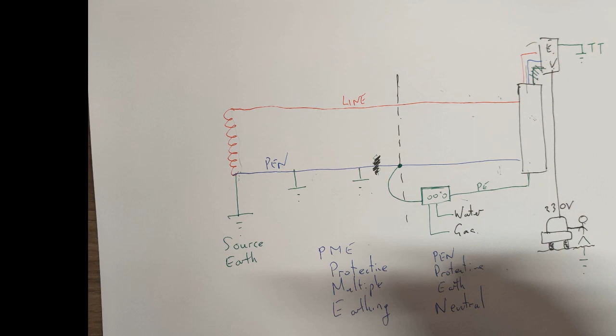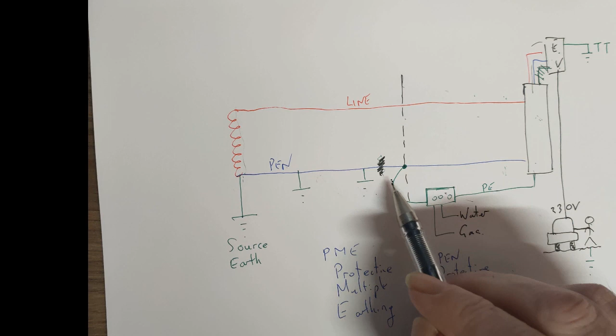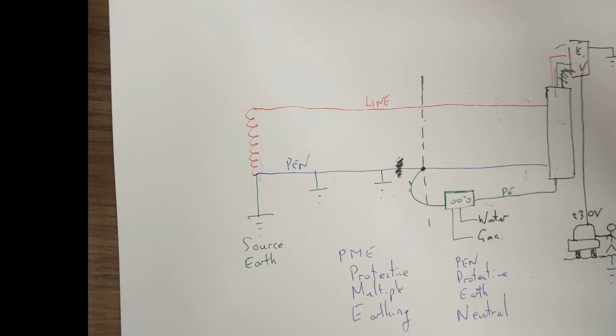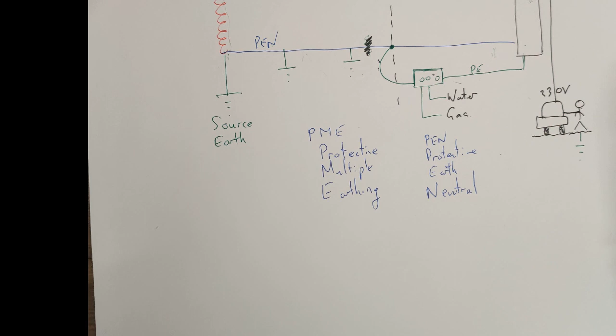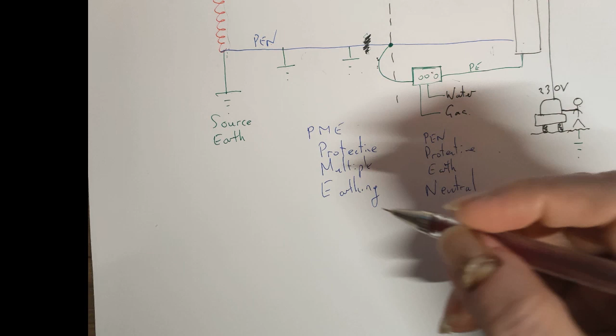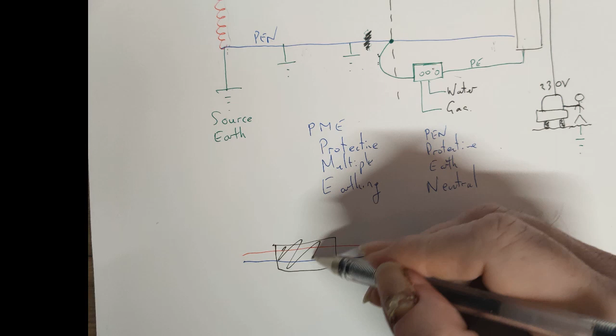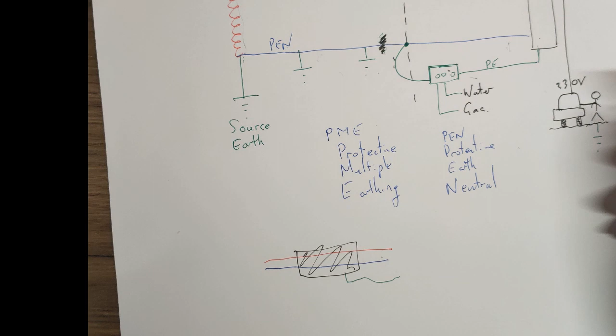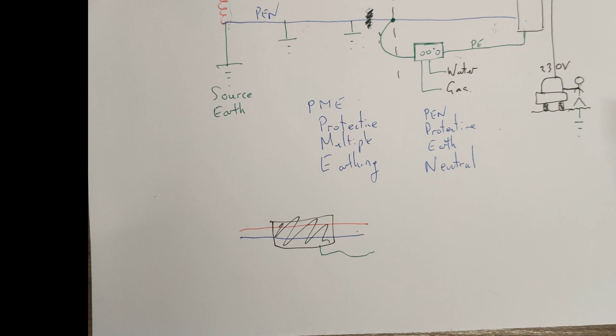Now, you might think that this is unique to a TNCS system, and you'd be right. If you did indeed have a TNS system, then this wouldn't occur, because the TNS system takes its earthing from the sheath of the cable. However, let's say there's a break in a TNS cable. So you've got in the TNS system, underneath your road, there's your line, there's your neutral, and your earth. Let's just draw the cable over the top. There you go. And your earth is coming from the sheath of the cable. Okay, so it should be a straight line. There you go. Now, there's a break in that cable, and it has to be repaired.